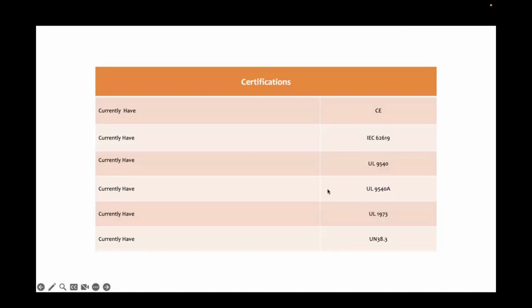We're really happy about our certifications too. We've been working hard on this. Currently we have our CE certification as well as our IEC 62619. Also we have UL 9540 with the Sol-Ark 15K and 12K inverter. We also have our UL 9540A fire test safety code, allowing us to install in even the most strict jurisdictions. Also have the UL 1973, and lastly the UN 38.3 certification as well for the V5 battery.